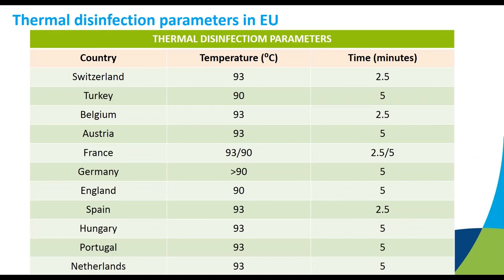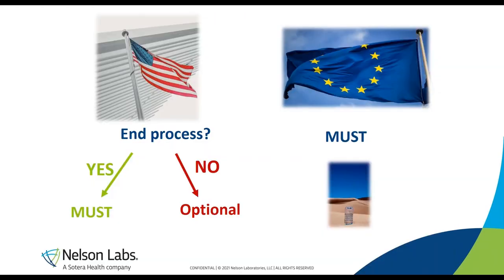Here is a slide giving an overview of different thermal disinfection parameters for different countries in Europe. The A₀ method is preferred in Europe, with values of five minutes at 90°C or two and a half minutes at 93°C being standard. This gives you an idea that the parameters are more or less aligned across European countries.